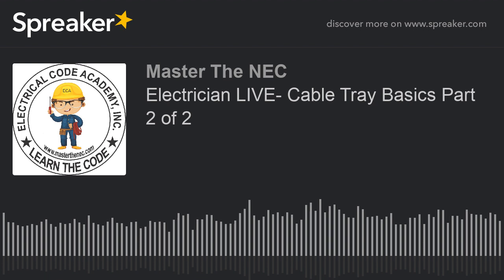Okay, so let's start first. 392.80(A) says this is the ampacity of cables rated 2,000 volts or less in a cable tray. Now, when we say cables, we're also talking about single conductor cables, and we kind of described that in part 1 of this series. But again, it's also talking about single insulated conductors as well. Okay, because again, 392.10 introduced single insulated conductors.